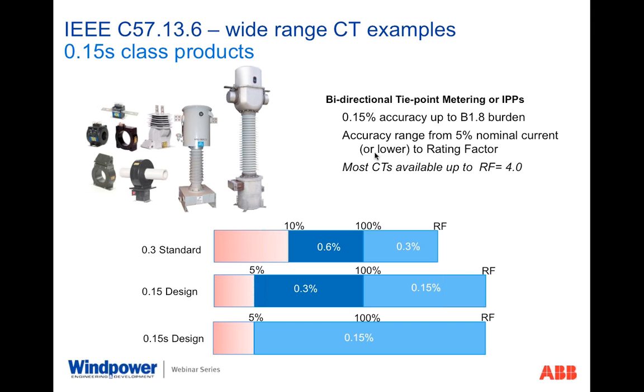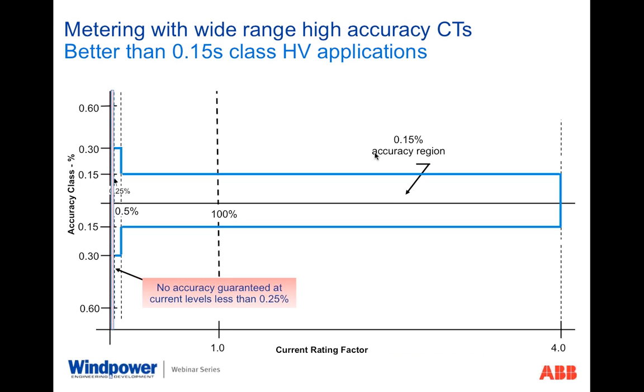One of the issues relative to measuring wind farm applications was that we have a better than 0.15 class design, and this actually existed before the IEEE developed their standardized accuracy ratings. So this was developed really listening to users like you and identifying what your needs were and providing a solution to your problems. And that came about 12 years ago when we saw the 0.3 and said, oh, this will not work for this application. What can we do to make this product better? So we focused on that particular task and came up with some rather phenomenal material that we could use to allow this unit to expand its measurement range and maintain accuracy, stability, all the way down, in our case, all the way down to 0.5% of nominal current.